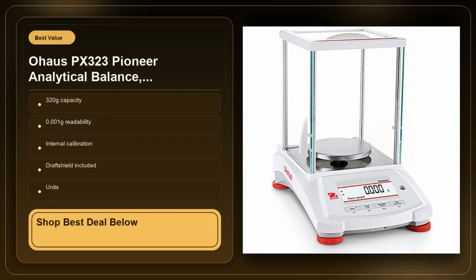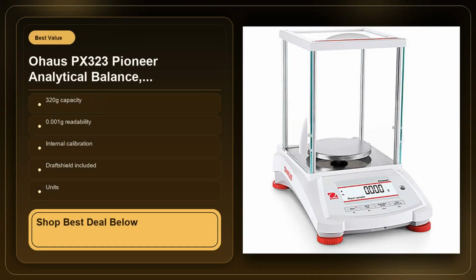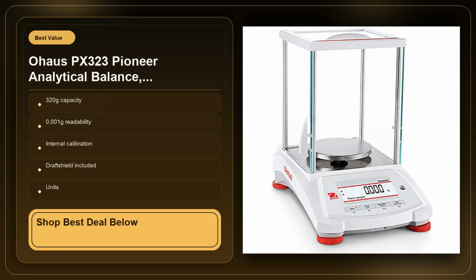Power options are also worth noting. The PX323 can run off AC power or a rechargeable battery, giving you flexibility if you have an occasional need to move the balance between benches. In a field-type lab or a mobile testing setup, the battery mode can keep you running for a few hours, but you'll quickly discover that the internal calibration routine drains a bit more power than a simple digital scale would. So, plan on keeping it plugged in for a 24/7 lab.